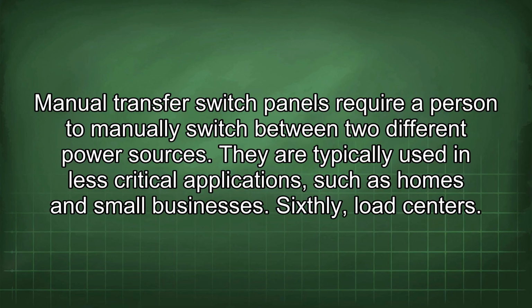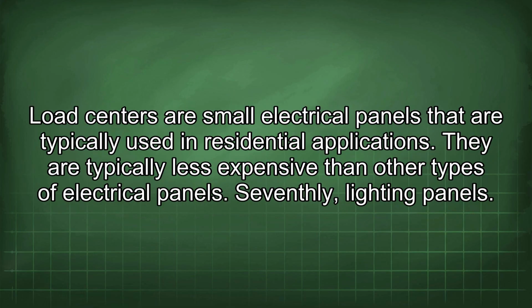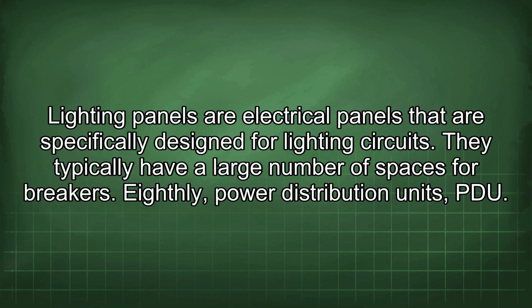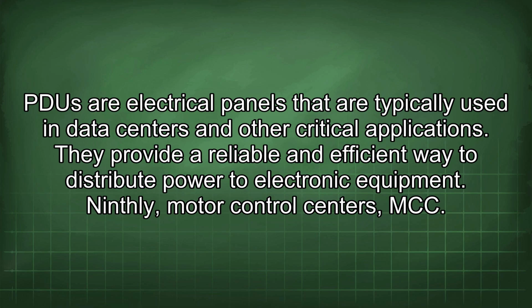Sixthly, load centers. Load centers are small electrical panels that are typically used in residential applications. They are typically less expensive than other types of electrical panels. Seventhly, lighting panels. Lighting panels are electrical panels that are specifically designed for lighting circuits. They typically have a large number of spaces for breakers. Eighthly, power distribution units, PDU. PDU are electrical panels that are typically used in data centers and other critical applications. They provide a reliable and efficient way to distribute power to electronic equipment.